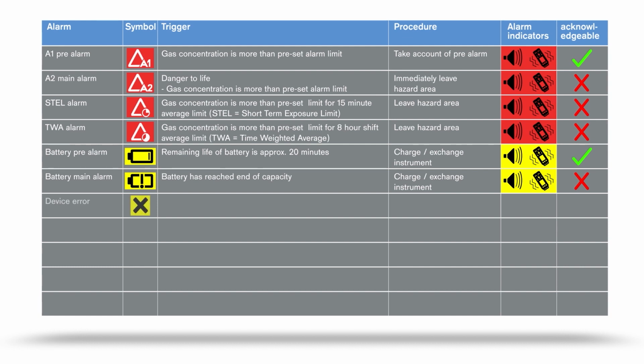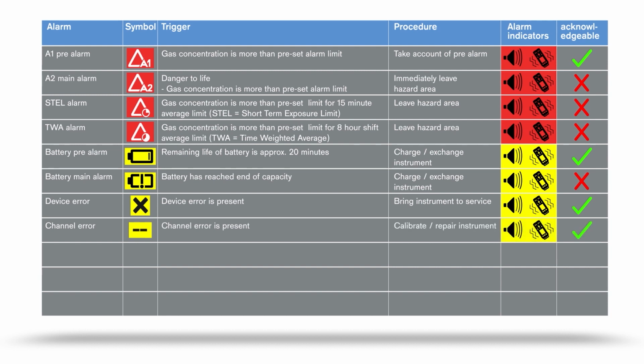If the instrument has an error present, an X symbol appears in the display. Once the alarm has been acknowledged, this symbol remains in the status line. Details of the error are shown in the Info menu. Resume your work with a different device and hand the faulty device to the service department. In case of a channel error, the device will need to be calibrated or possibly repaired. In case of a significant overrange, i.e. excessive concentration of flammable substances on the Cat-X channel, a blocking alarm is triggered. This alarm can be acknowledged by manually switching off the gas detector and switching on in fresh air.